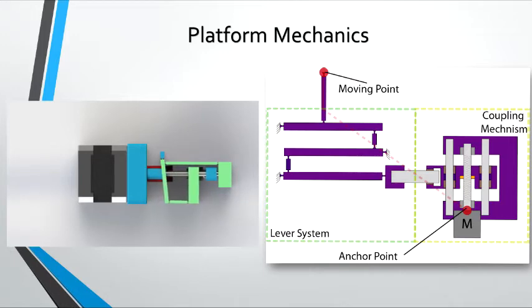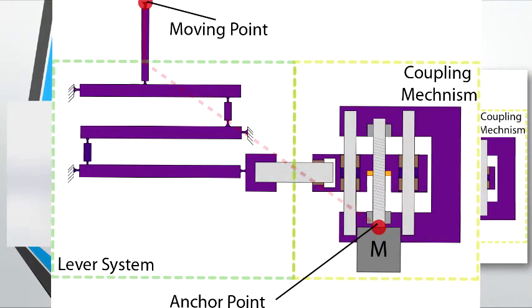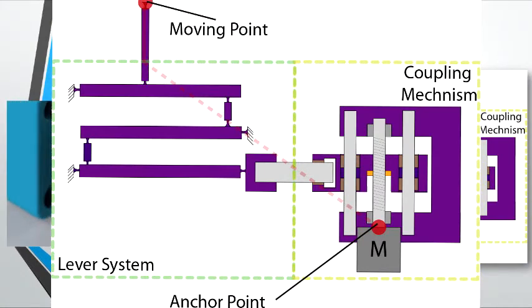Our stage needs to move in 1 micron increments over the range of 10 millimeters. In this design, we used a stepper motor to create precise rotation without feedback controls. To convert the rotation of the stepper motor into linear motion, we used a lead screw and a lead nut. The shaft of the lead screw is coupled to the shaft of the motor using a rigid coupling, and the nut is fixed to the lever system input.